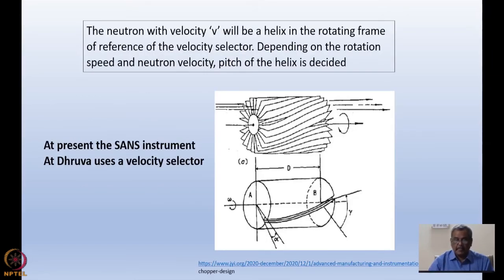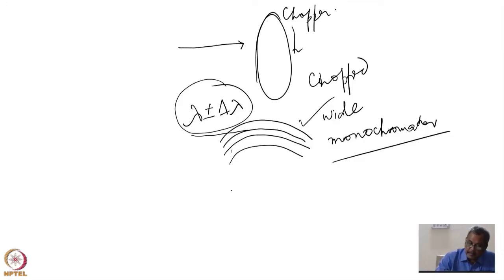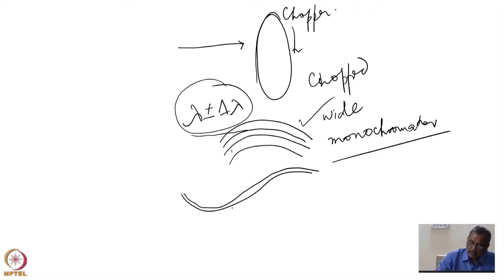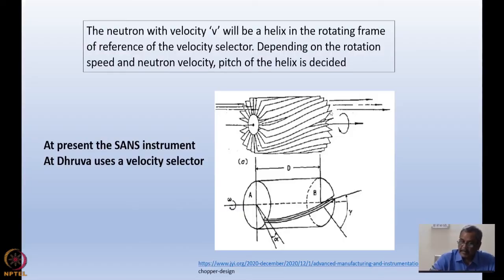The velocity selector is a cylindrical body on the surface of which there are slots at angle alpha following a helix. In a rotating frame, the neutron follows a helical path, and the rotation speed dictates this helical path and the wavelength allowed to pass. There is also a wavelength width determined by the slot width. Parallel helical slots are machined into the material and placed in the beam path.